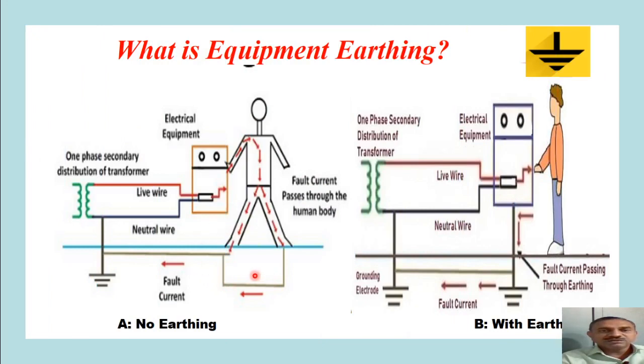So the first figure shows when no earthing is done to an electrical equipment. Here you can observe the electrical equipment which is given the electricity supply from a distribution transformer. For example, we are considering it as single phase. The neutral of it is also earthed. Now the equipment is being touched by a human being. As the equipment is not earthed, it means that its enclosure and all the metallic parts are not earthed. When a certain fault has taken place inside the electrical equipment, the body of the electrical equipment is now in direct contact with the live wire. So it is having the voltage of the live wire. Suppose in India we consider it as 230 volt.